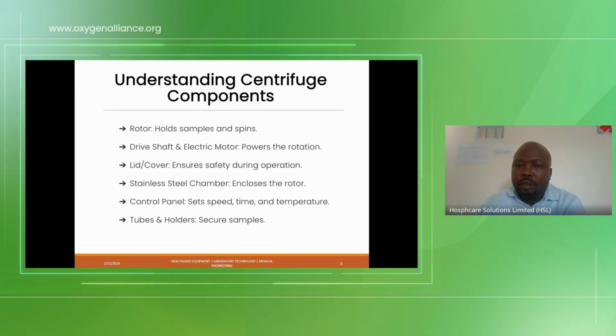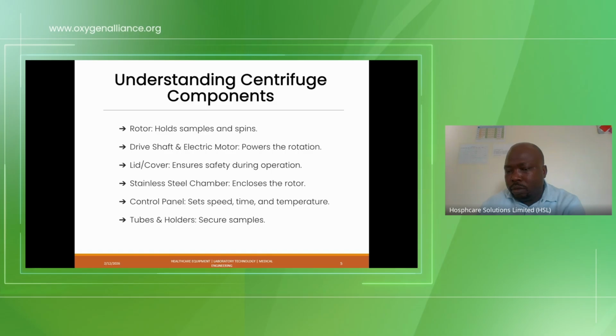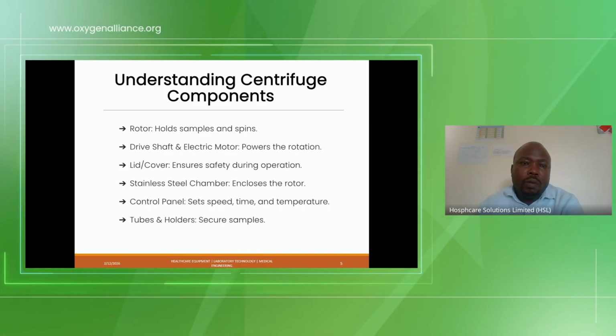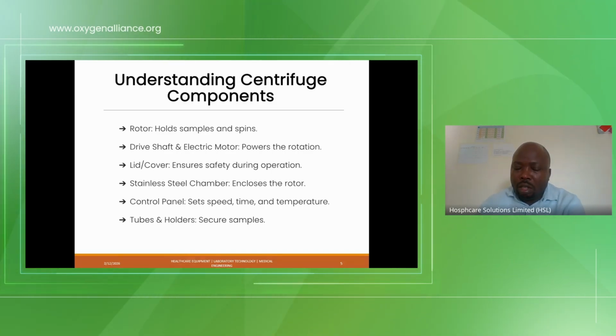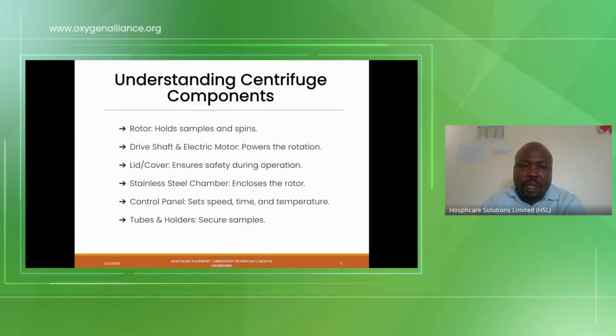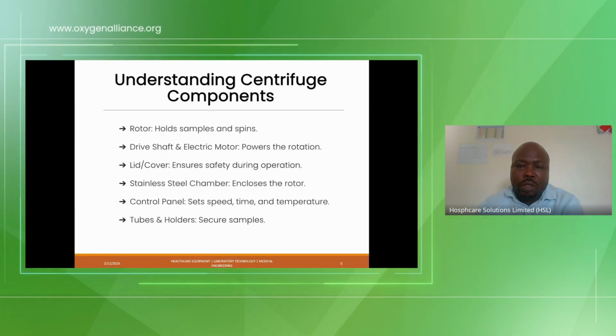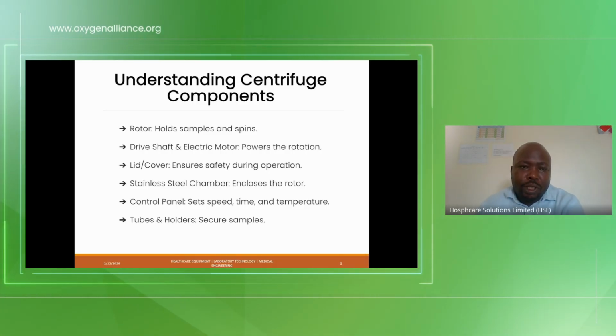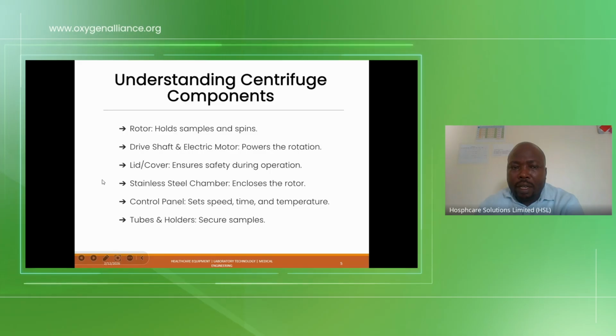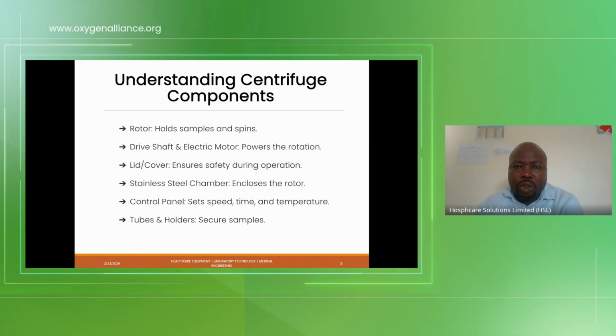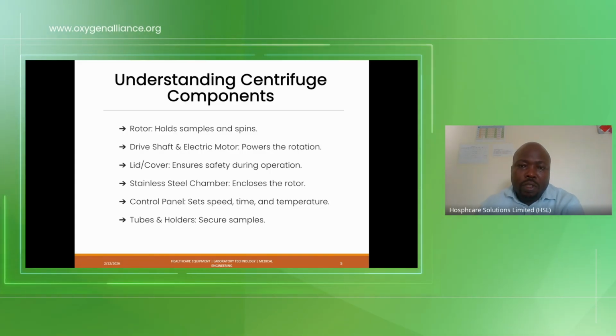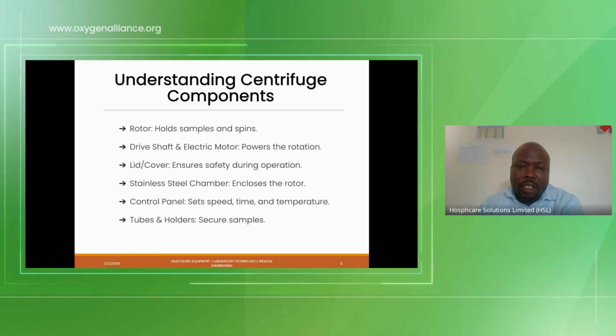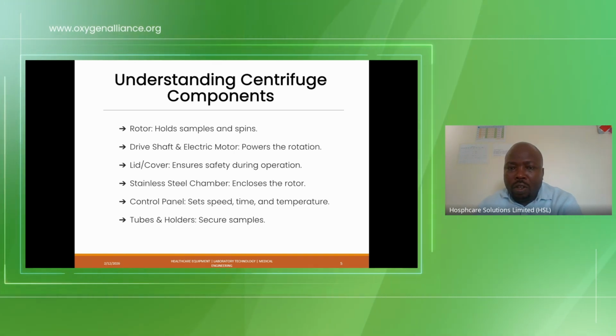We have a rotor that holds the sample during the spinning. We have a drive shaft in attachment with an electric motor, which is controlled by power to create a rotation. We have a lid or cover to ensure safety for the user. We have a stainless steel chamber which encloses the rotor.